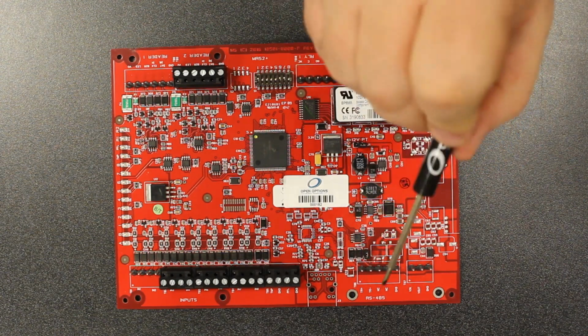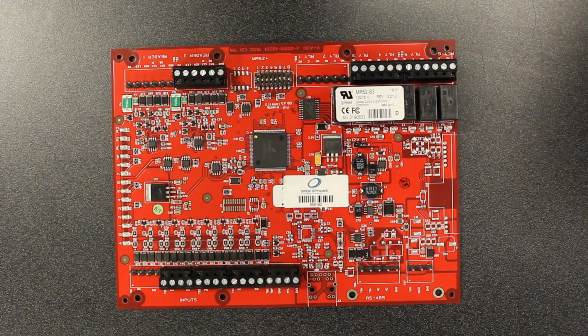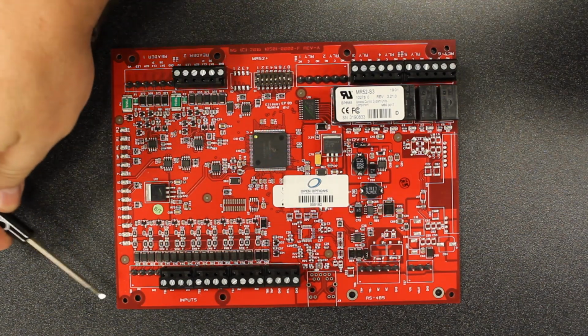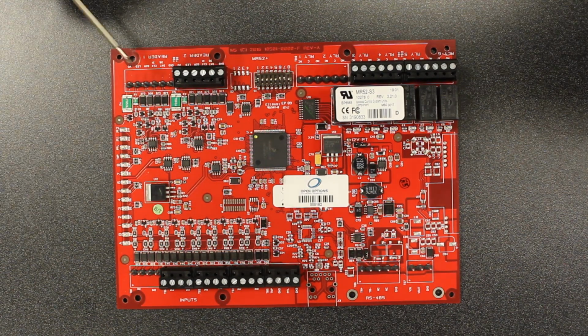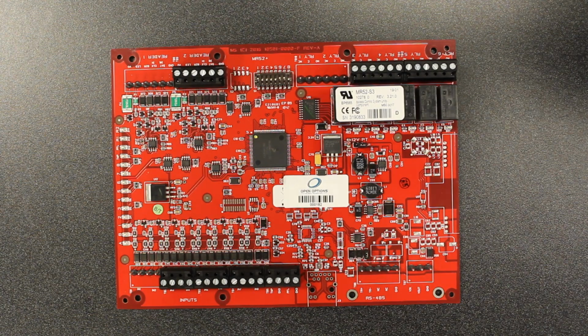485 connection, TR plus goes to plus, minus to minus, ground to ground. Here's my inputs, 1 and 2, and my reader port, and my relay.